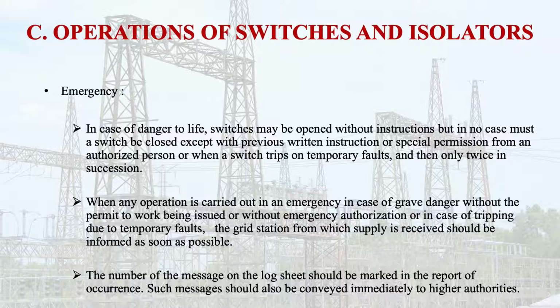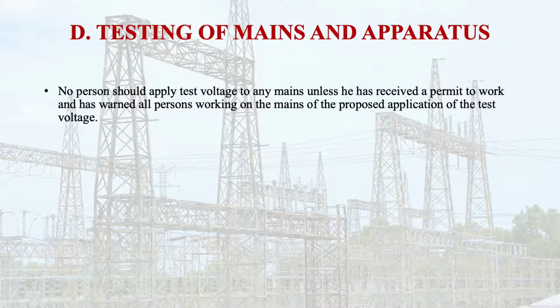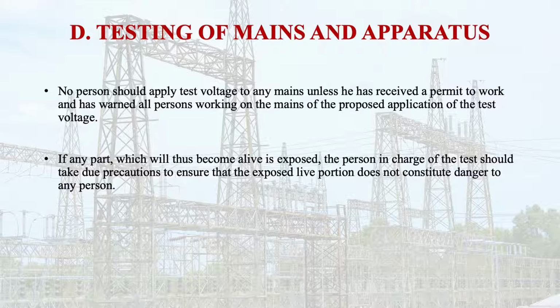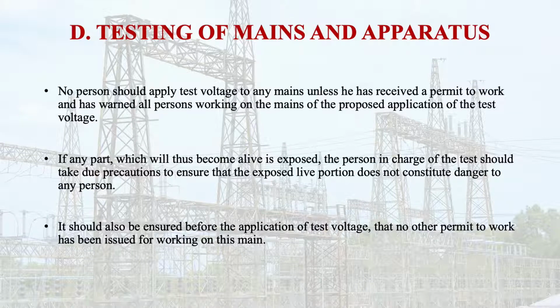So learners, now let us discuss the testing of mains and apparatus and the safety instructions associated with this. No person should apply test voltage to any mains unless he has received a permit to work and has warned all persons working on the mains of the proposed application of the test voltage. If any part which will thus become alive is exposed, the person in charge of the test should take due precautions to ensure that the exposed live portion does not constitute danger to any person. It should be ensured before the application of the test voltage that no other permit to work has been issued for working on this mains.